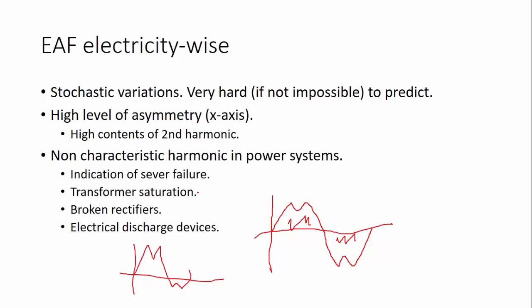Now, normally in a system, when you have second harmonic pollution, it means that something is very wrong. A transformer is saturated, some rectifiers are broken or about to break, or you have some electrical discharge somewhere in the system, maybe partial, maybe full, maybe intentional because of an electric discharge device. But normally in electric systems, you do not have second harmonic or even harmonics. Let's say 2, 4, 6 are harmonics that normally don't exist, but in an arc furnace, you do have a lot of second harmonic.